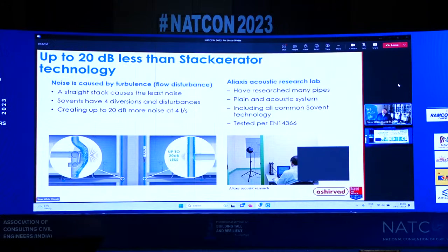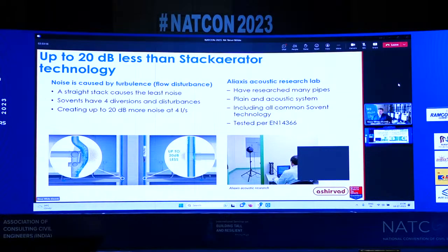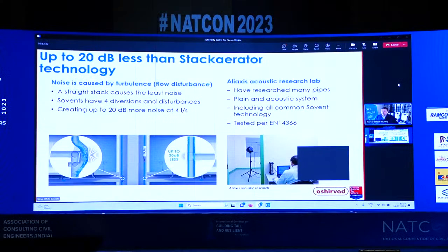Acoustics - active drainage ventilation is where we get a change of direction, which generates noise. With a Stackaerator system, we tend to generate 3 points of noise as it flows and tries to slow the flow down. With the active system, we're not interrupting the flow at all. We know water falls at 3 to 6 meters a second, terminal velocity - so the discharge of water from the Burj Khalifa is the same speed as from a 2 or 3 story building, since water reaches terminal velocity after about 1 floor's drop. But if we have a change of direction and want our soil system to be quiet, we don't want to interrupt the flow. With an active system, we're not generating that point of noise.